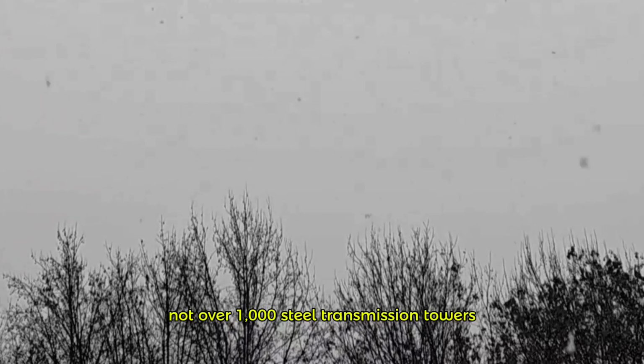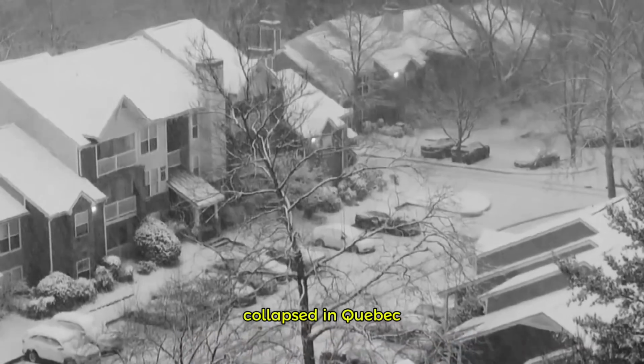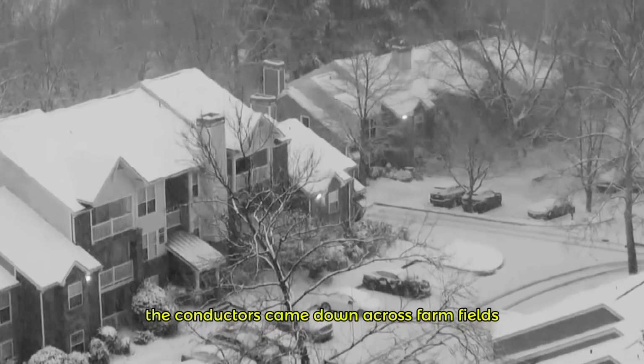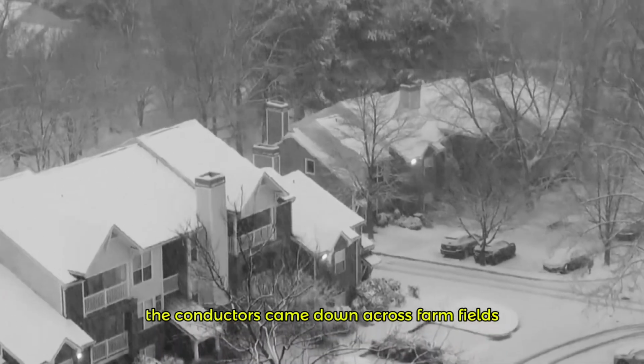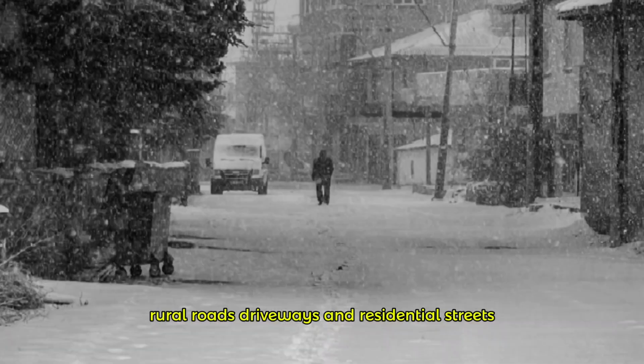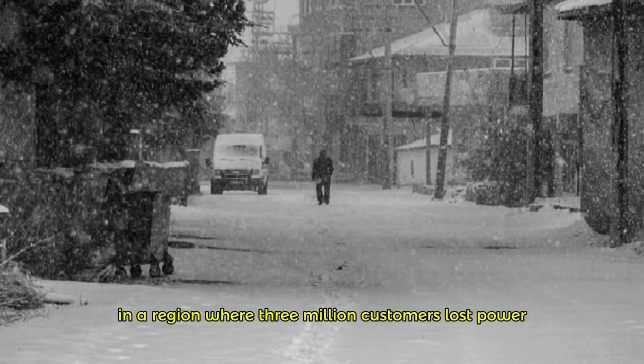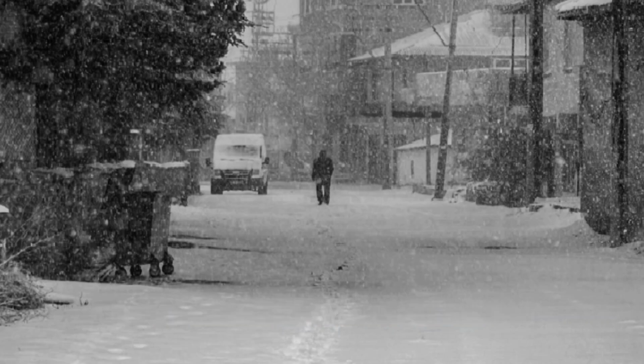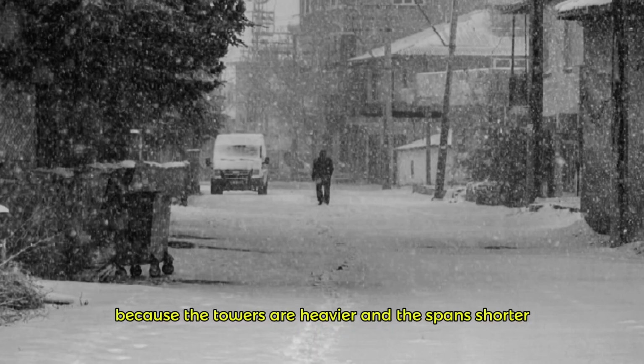Now, over 1,000 steel transmission towers collapsed in Quebec. The conductors came down across farm fields, rural roads, driveways, and residential streets in a region where 3 million customers lost power. The lines that failed first were not the 735 kilovolt backbone. The backbone held longer because the towers are heavier and the spans shorter.